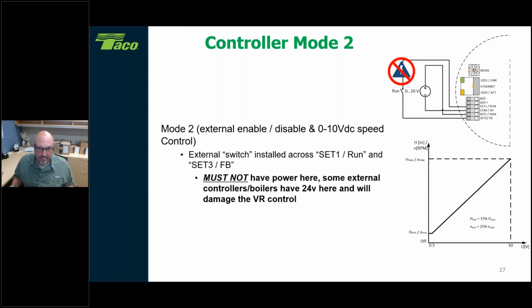This is not where you connect your power terminals from an SR control. That would be 120 volts here, right? Yeah, it'd be 120 volts, and that wouldn't be good either. Right. So this is going to be strictly dry contact, 0 power on these 2 wires that go across set 1 and set 3. Okay.